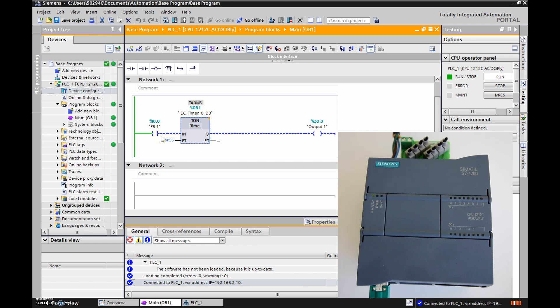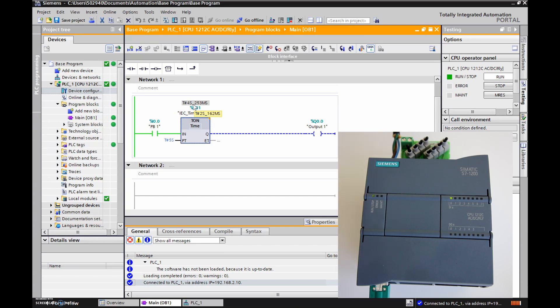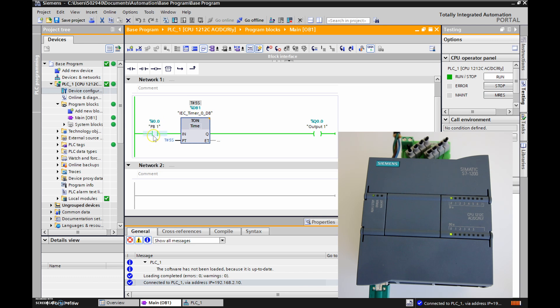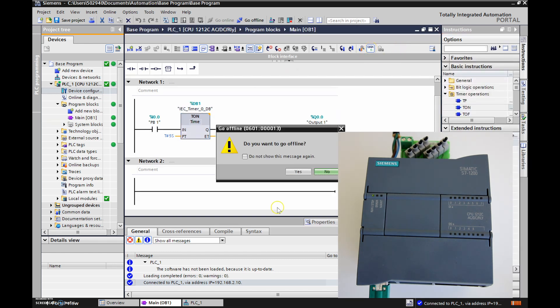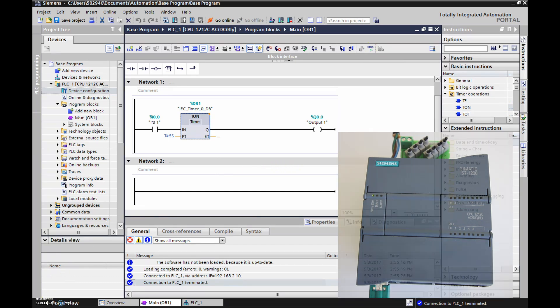If we count up to five but stop at three, the output should never turn on because the preset has to equal the accumulated value — we have to reach five seconds. Let's close the switch: one, two, three — then open it. The output never fired. In order for the on-delay timer output to go from zero to one, we must increment all the way to five seconds: one, two, three, four — then it turns on. As soon as logic continuity is lost the output turns off, exactly like an on-delay timer.